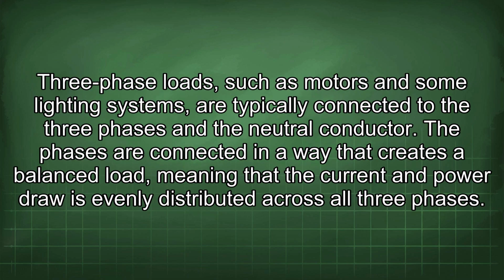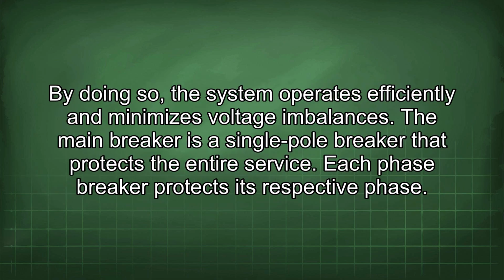3-phase loads such as motors and some lighting systems are typically connected to the 3 phases and the neutral conductor. The phases are connected in a way that creates a balanced load, meaning that the current and power draw is evenly distributed across all 3 phases. By doing so, the system operates efficiently and minimizes voltage imbalances.